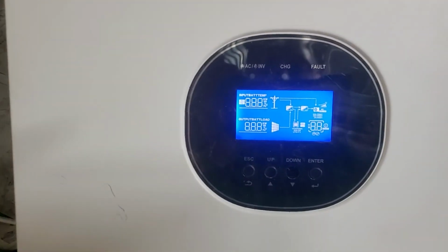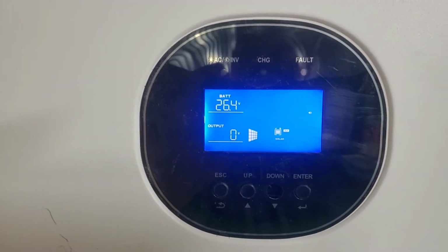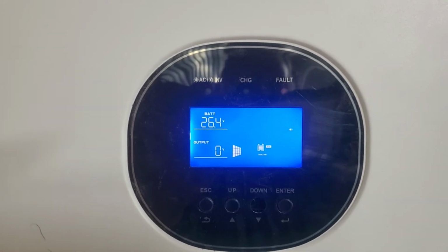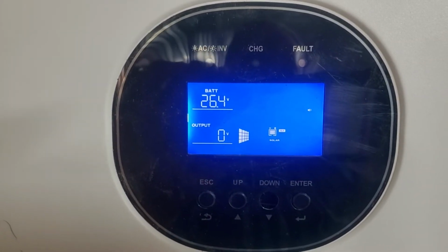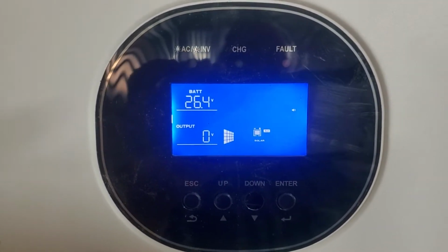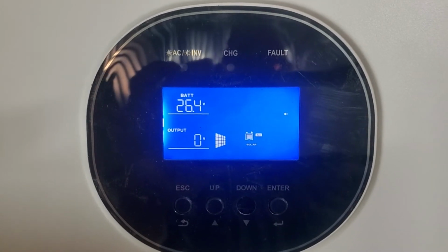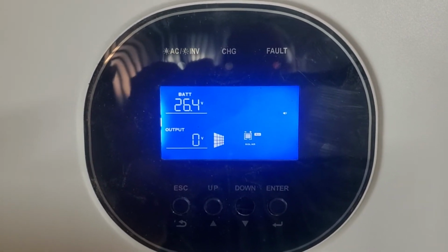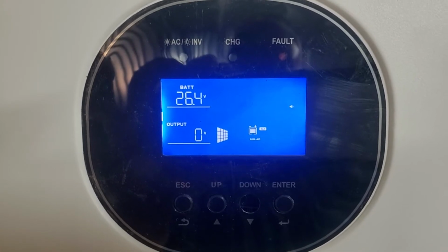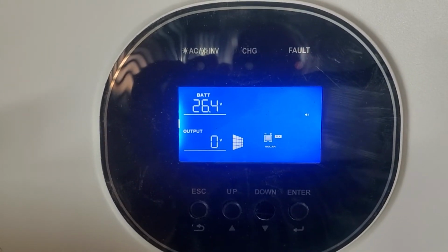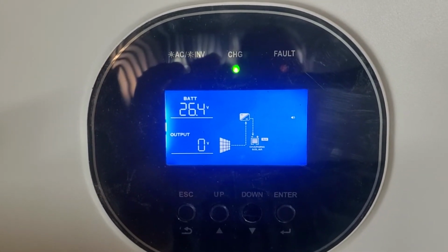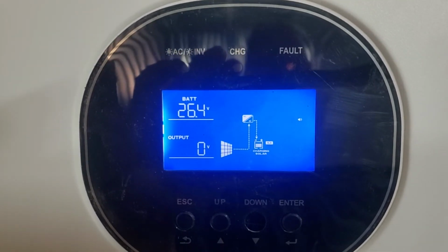Now it's going to try and charge the battery, which is at 26.4 volts, and you'll see that voltage will spike up because the BMS is fully charged and just ready to trip on over voltage. You can see there, it's charging. Now watch the battery voltage very carefully.